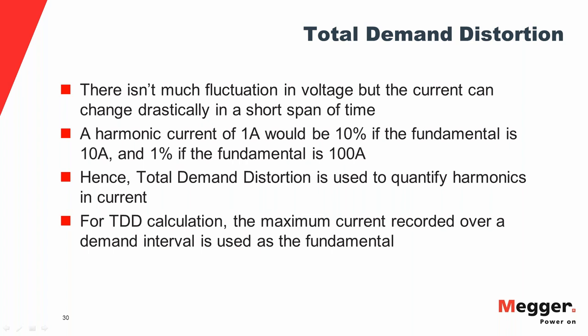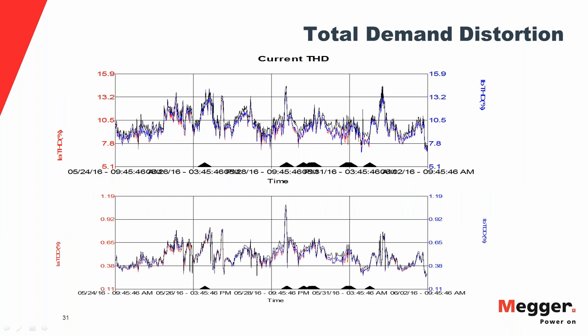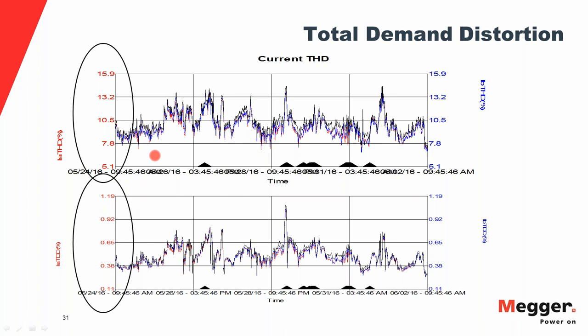Comparing THD and TDD charts from the same recording — THD on top, TDD below — they follow the same pattern, but the Y-axis values differ drastically. THD ranges from 7.8% to 14%, while TDD values remain within about 1%. This illustrates why TDD is a more stable and meaningful metric for current harmonic analysis.